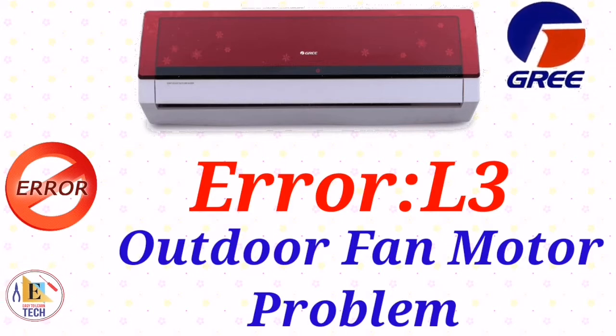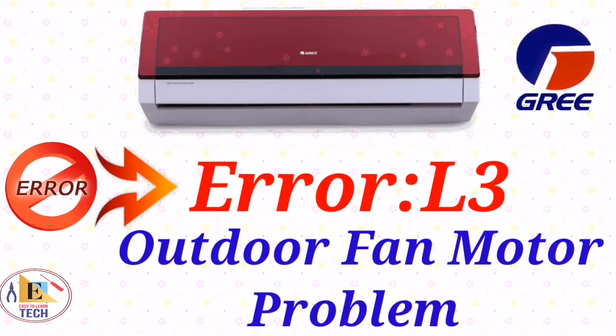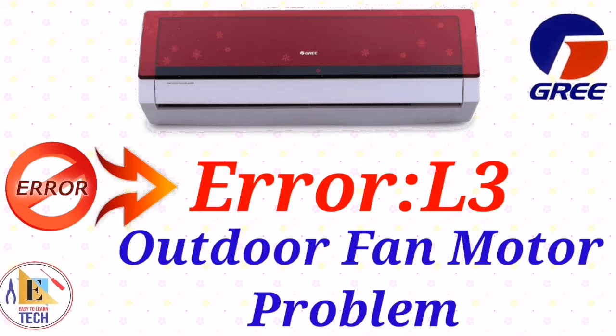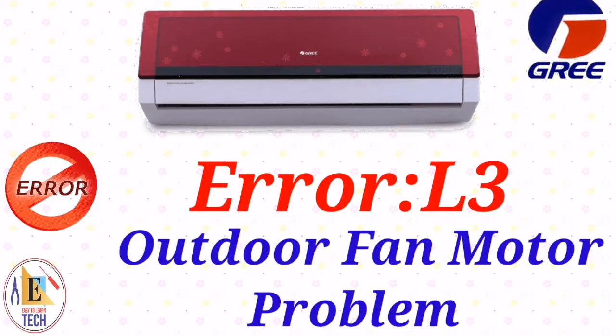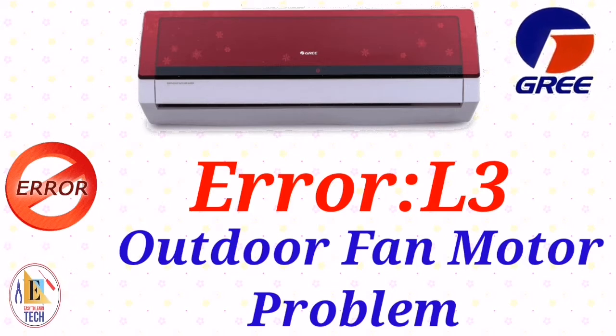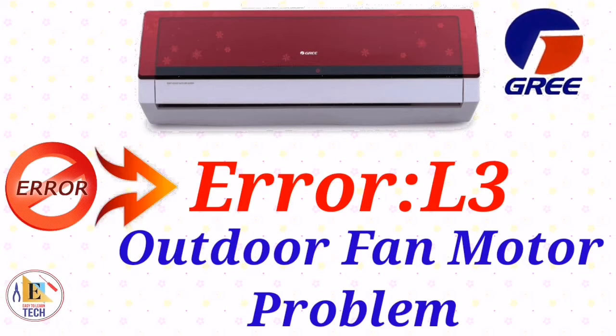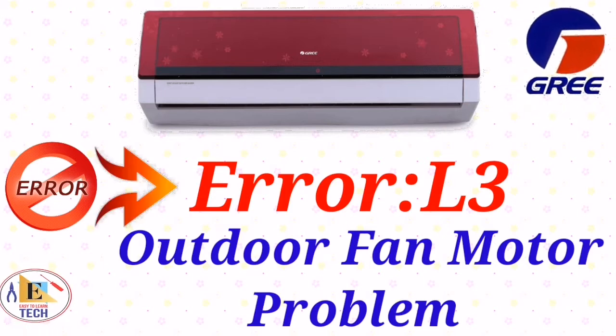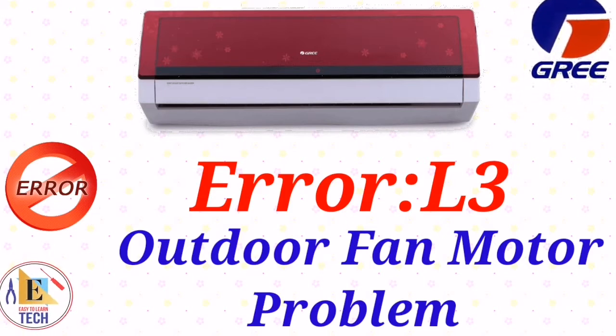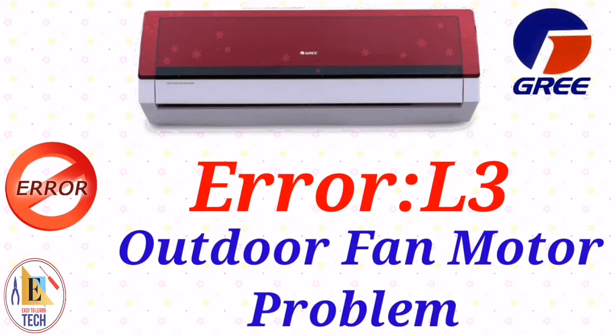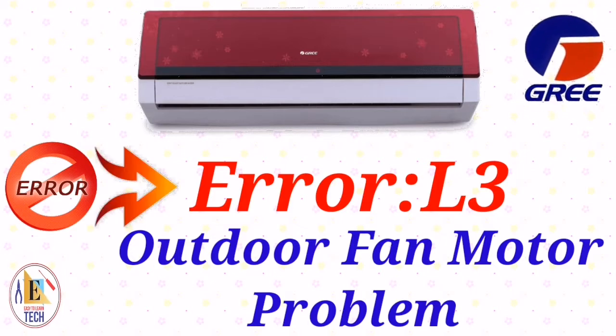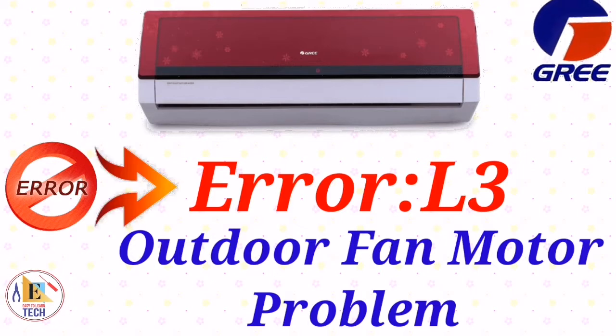And if you get the same error L3, then you have to check the outdoor power supply which is going to our outdoor fan motor. If the power supply is not perfect, then you have to change the outdoor PCB. And then you can check the resistance of our outdoor fan motor. If the resistance is not good, then you have to change the outdoor fan motor and you will get the solution of this error.